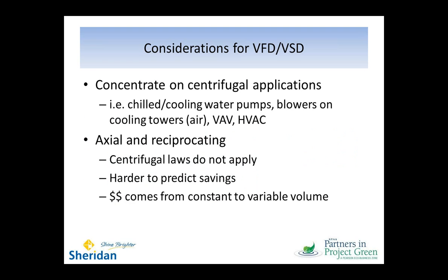So, considerations then for your variable frequency drive or variable speed drive: concentrate on those centrifugal applications. So find those cases where you've got cooling water pumps in, and often what's recommended is the cycling of fluid out to cooling towers and things like that that's valuable, as opposed to circulating your process fluid out to your process, because that can tinker with a lot of different set points. But you've got easy opportunities on cooling towers, the blowers, the variable air volume equipment, your heating, ventilating, air conditioning equipment. All of that kind of stuff is ripe with opportunities for variable speed drives.